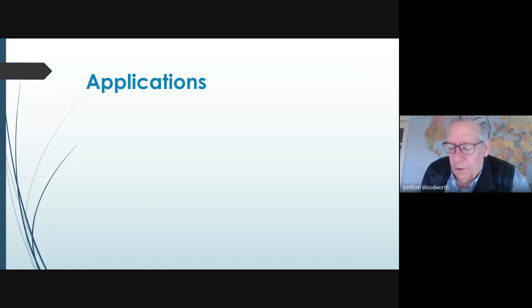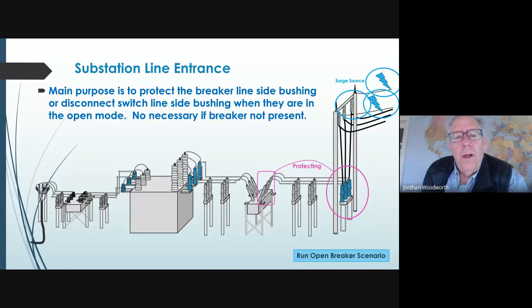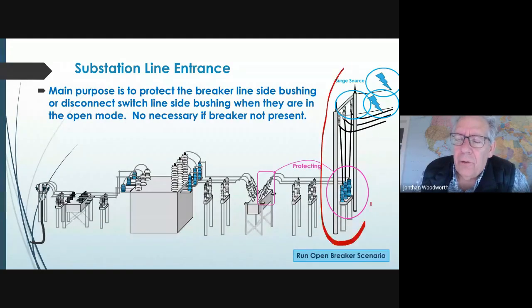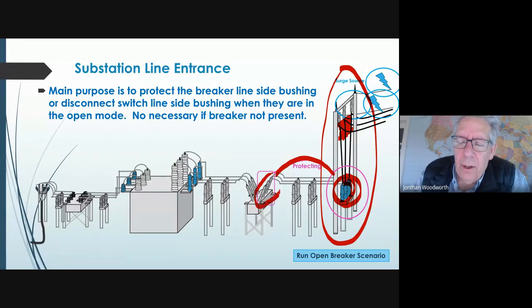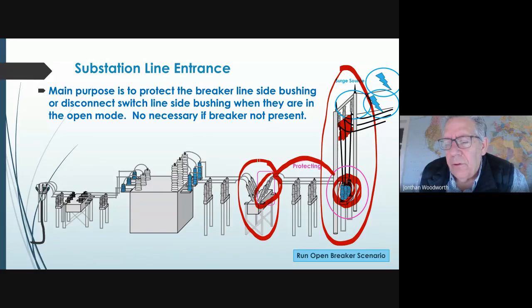So for the next few minutes, then, I want to talk about the different types of application of arrestors. In a substation, there's about 3 or 4 places where you'll see arrestors, and each location is protecting certain things. For instance, we call this the line entrance to a substation, and sometimes you'll see arrestors either up here or high on the tower or down low, and the real purpose for these arrestors is to protect the bushing on the breaker. You don't usually see arrestors on the line entrance if there is no breaker. So this arrestor protects these bushings, and we can't go into the details of that, but that's its purpose.